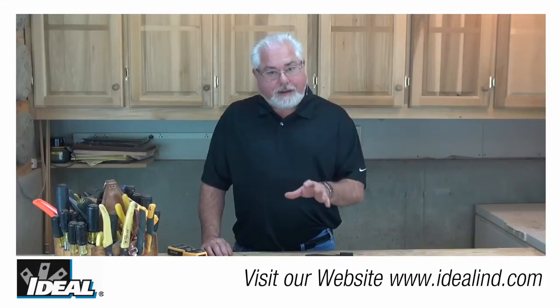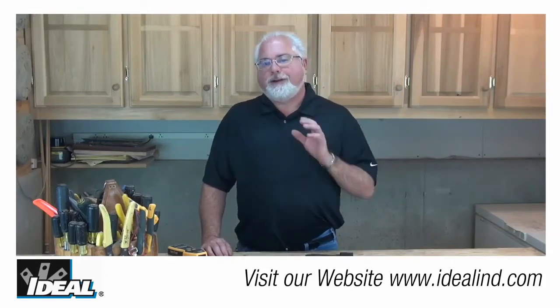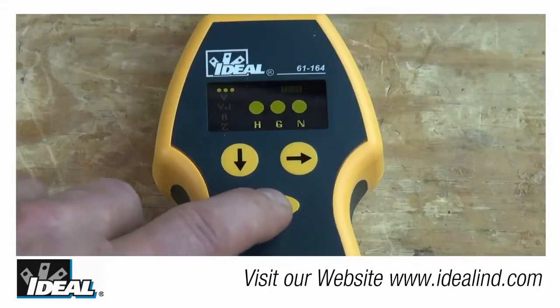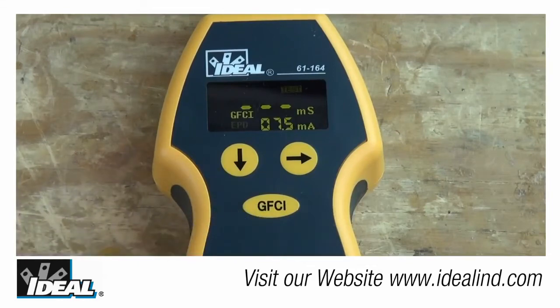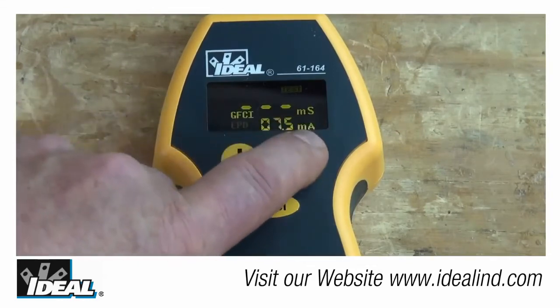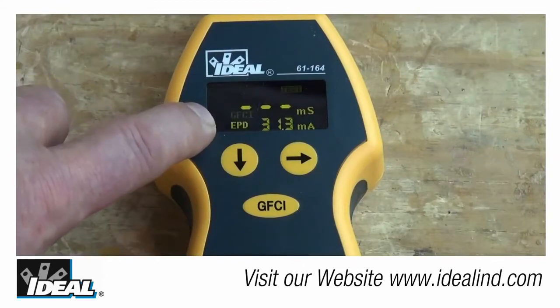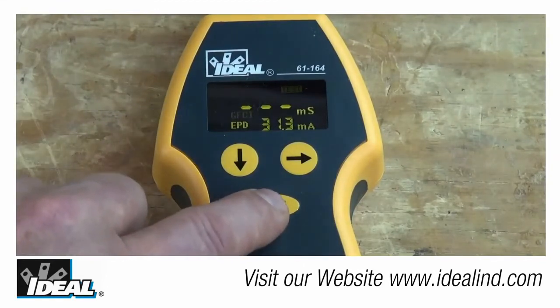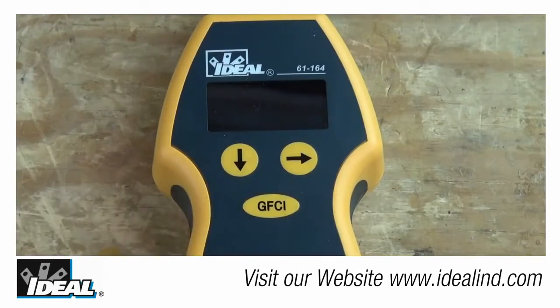Now, to conduct that equipment protection test, press the GFCI button once to enter that GFCI main menu. Then press the right arrow button to highlight the EPD symbol. Then you're going to press the GFCI button one more time to activate that test. Now, again, the actual current being leaked to ground is displayed. The test icon and hourglass symbol are going to appear on the display to let you know that the test is being performed.